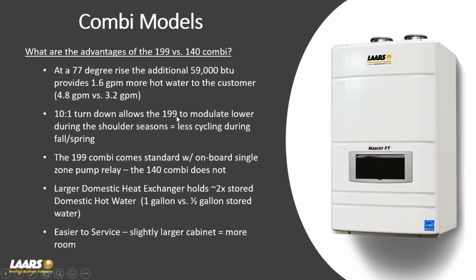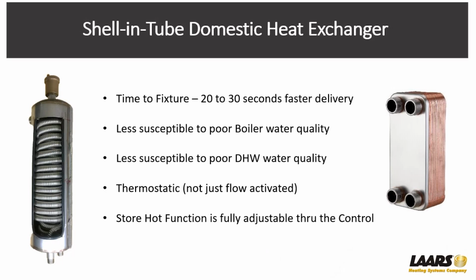So on a 199,000, if you only need 120,000 at full load, let's say you've got 3 zones, let it do its job. Let it modulate down. It may never need to go to high fire. Maybe if it's a 0-degree day out and you've got all zones running, it might have to, but then it's going to modulate right back down. So that's the difference on the advantages of a 199 versus a 140.